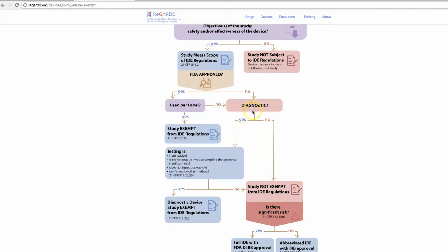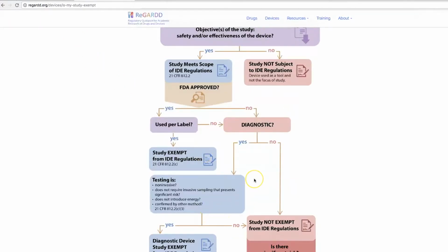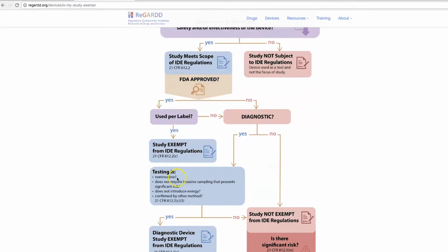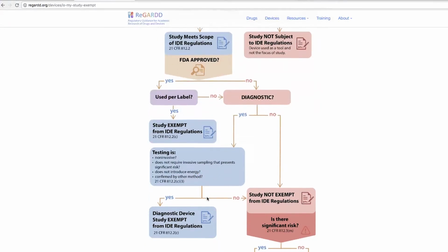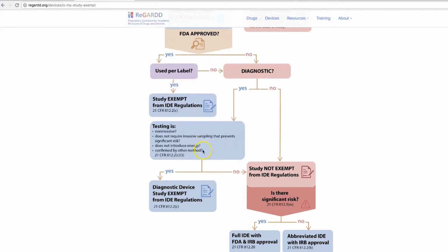Now over here, if you answer yes, the device is being used as a diagnostic, then we have some criteria that we need to consider. And that is, does the testing involve invasive or non-invasive procedures or invasive sampling that presents significant risk? Is energy being introduced? That could be electrical, radiation, laser. Is the testing being confirmed by another standard care method?